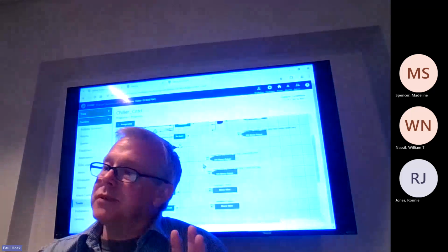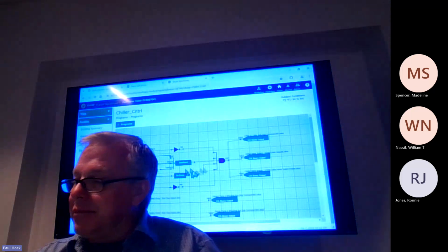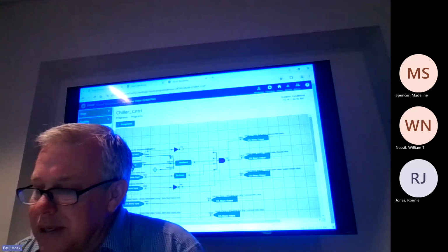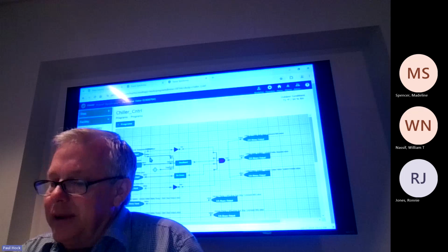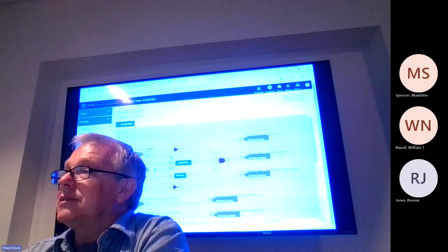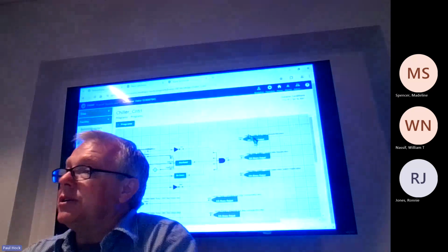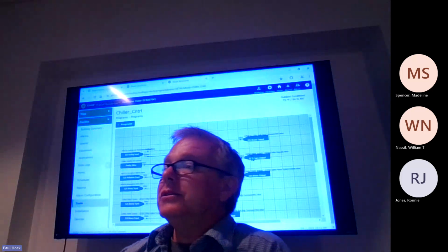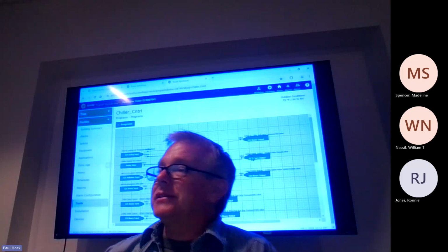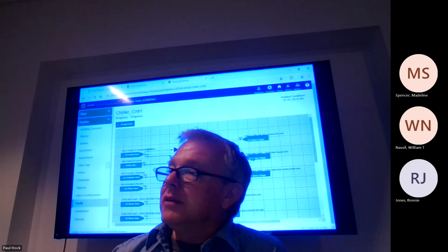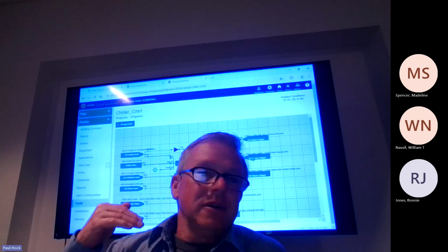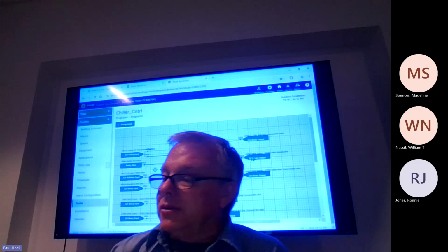So it's just a block type code programming. If my outdoor air temperature is less than, we'll say my outdoor air lockout, which is 45 degrees, it's going to turn off my chiller. So there is an outdoor air lockout on this chiller. Anything below 45 degrees is going to shut the chiller down. Air handler's still going to run. It's going to say, hey, I'm too cold to be running a chiller. I don't need it. I should be using outside air. And if everything's good, dew point's good, outside air temperature is good, it'll shut your chiller down for you.